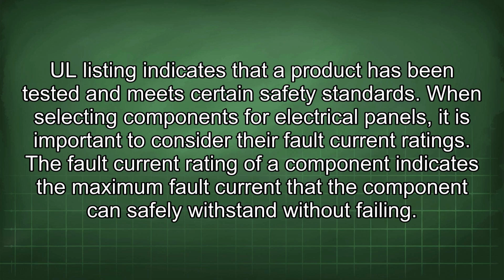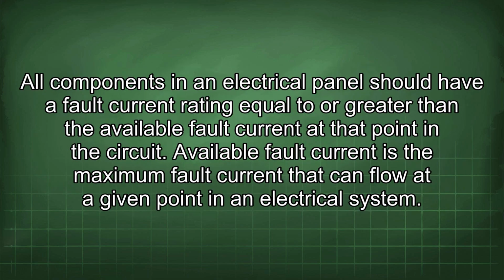When selecting components for electrical panels, it is important to consider their fault current ratings. The fault current rating of a component indicates the maximum fault current that the component can safely withstand without failing. All components in an electrical panel should have a fault current rating equal to or greater than the available fault current at that point in the circuit.